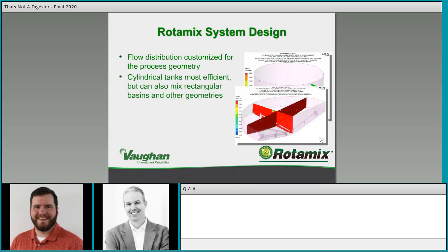Rotamix system design can distribute flow for customized process geometry. Cylindrical tanks are the most efficient, but we can mix rectangular basins and other geometries. A cylindrical tank with perfect symmetry tends to lend itself to good energy efficiency and transfer, but rectangular basins can sometimes provide better shear and turbulence which agitates more at a cost of energy. There's a CFD analysis shown here where an old clarifier was transitioned to a sludge storage tank.